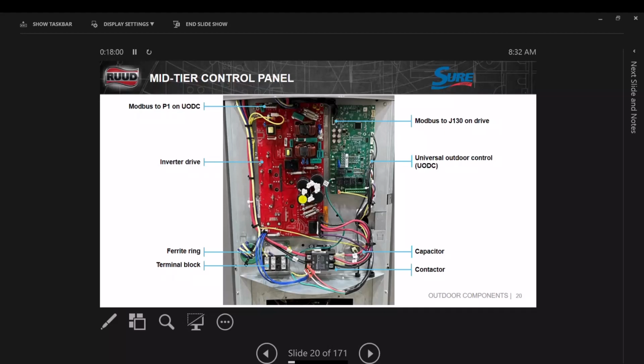The contactor, when the unit runs and it gets up to 75% on the inverter, and you have to go into 2nd stage, let's say, whenever that thermostat says it goes into 2nd stage, then it turns the inverter off and pulls in the contactor. I'm going to say this about a dozen times today. Do not push that contactor in while the unit is running in the inverter. There's nothing for service that matters if you push that contactor in. Other than when you push it in and the inverter's engaged, it blows the smoke box out of the board. That's out, and it can't be put back.